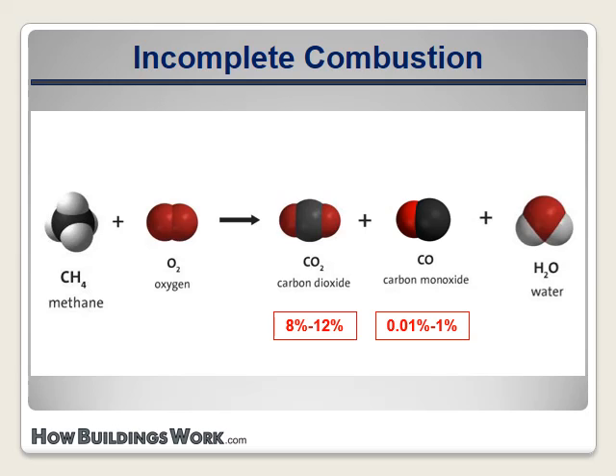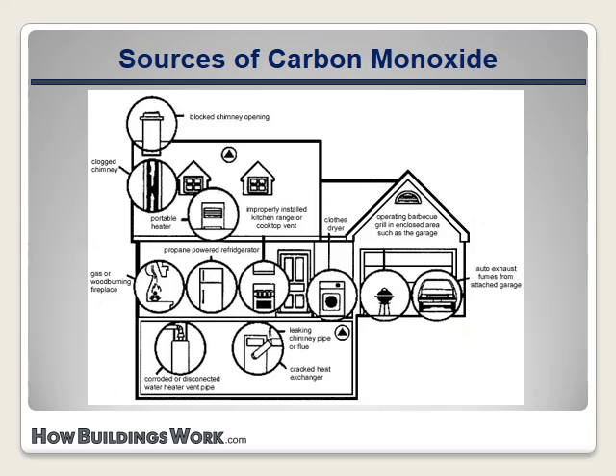Highly dangerous combustion gases might contain 10% carbon dioxide and 0.1 or 0.2% carbon monoxide. Carbon monoxide can be generated by any device in a building that burns a hydrocarbon fuel. The list is extensive. It includes automobiles, barbecue grills, central heaters, space heaters, water heaters, kitchen stoves, ovens, fireplaces, and clothes dryers.